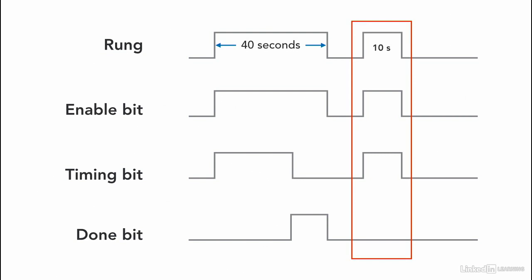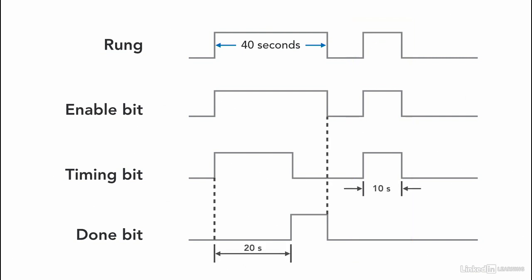So if the rung is only on or is only true for 10 seconds, then the enable bit will be true and the timer timing bit will be true. But the done bit will not get to be true because it will never reach the preset value of 20 seconds. So keep that in mind when using a timer and you notice that the done bit does not work.